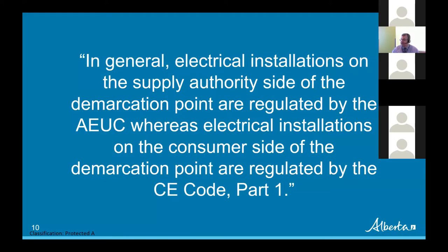One of the things that's come up in our conversations with the Safety Codes Council and their sub-council working groups is trying to clarify the point of demarcation between the utilities and the consumers. A key quote states: in general, electrical installations on the supply authority side of the demarcation point are regulated by the Alberta Electric Utility Code, whereas electrical installations on the consumer side are regulated by the CE Code Part 1, the Canadian Electrical Code Part 1.